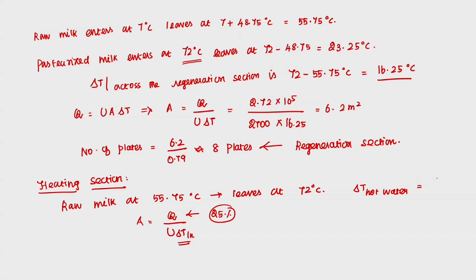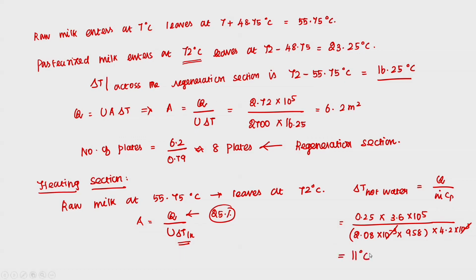So, we know Q is equal to m Cp del T. So, del T of the hot water is nothing but Q upon mass flow rate into Cp. Q I know, so 0.25 of my total Q is nothing but 3.6 into 10 to the power of 5, divided by the hot water mass flow rate, which is given, and we calculated 2.08 into 10 to the power of minus 3. This is a volumetric flow rate that has to be multiplied with the density, 958, into Cp. Cp is 4.2 into 10 to the power of 3, because it is given in kilojoules, this will get cancelled. So, we are getting the del T of about 11 degree centigrade.